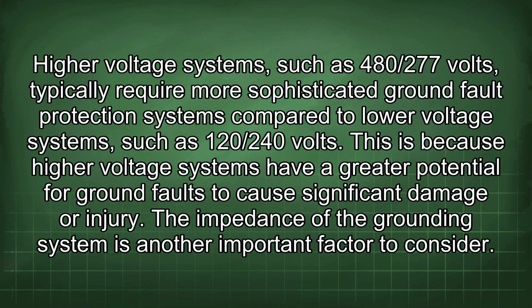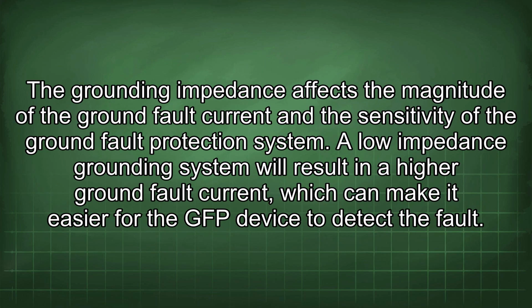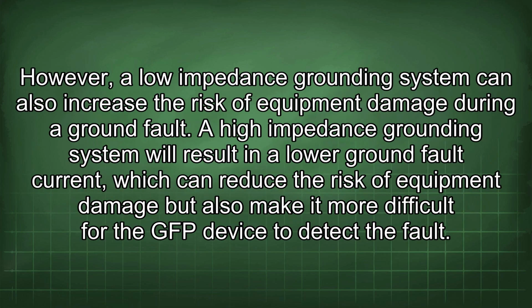This is because higher voltage systems have a greater potential for ground faults to cause significant damage or injury. The impedance of the grounding system is another important factor to consider. The grounding impedance affects the magnitude of the ground fault current and the sensitivity of the ground fault protection system. A low impedance grounding system will result in a higher ground fault current, which can make it easier for the GFP device to detect the fault. However, a low impedance grounding system can also increase the risk of equipment damage during a ground fault.